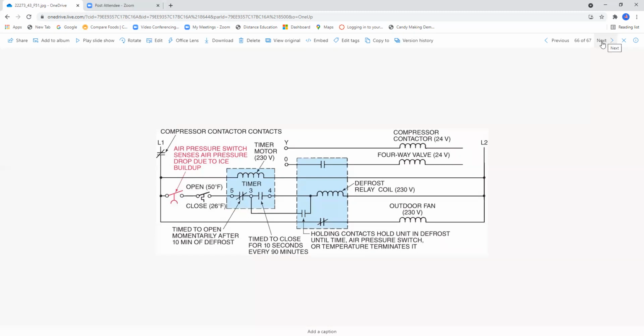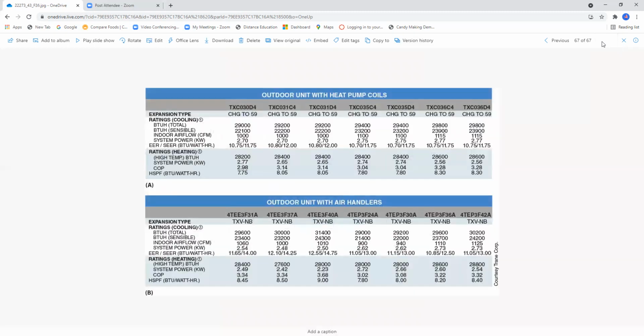And last but not least, here we have an outdoor unit with heat pump coils. This is a chart. One of the things when you install heat pumps, there are so many different variations out there. We cannot call your attention to just one heat pump. Manufacturers have specific specifications. They're going to show you what the BTU ratings are depending on the coil combinations. This particular chart here, see if I can find that for you. See if it's in the textbook.